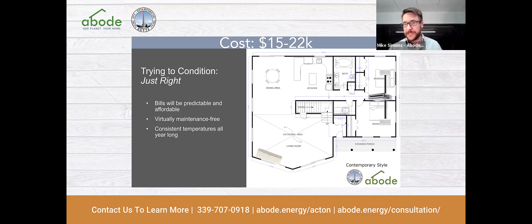The reason for this is most bedrooms, let's say 200 square feet, the heat load of that space on the coldest day of the year is probably 4,000 BTUs. The smallest ductless piece of equipment is 6,000 BTUs, so it's over a third oversized on the coldest day of the year. Most days aren't the coldest day, so it's always going to be wildly oversized. That's why we like ducted units - you can really match the capacity of the load of the rooms with the capacity of the units.